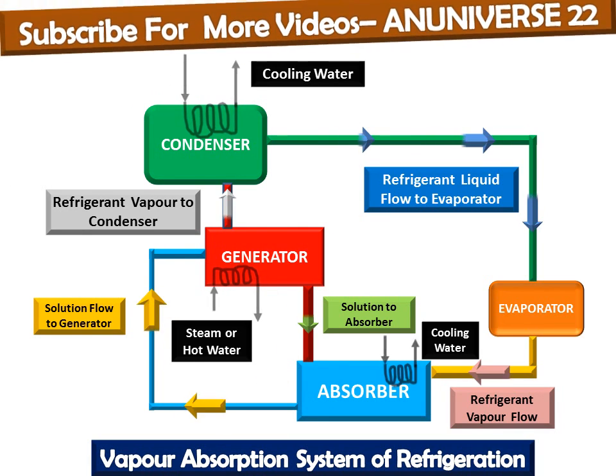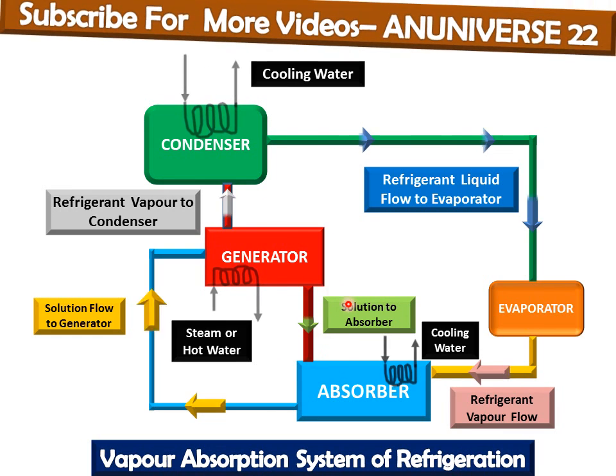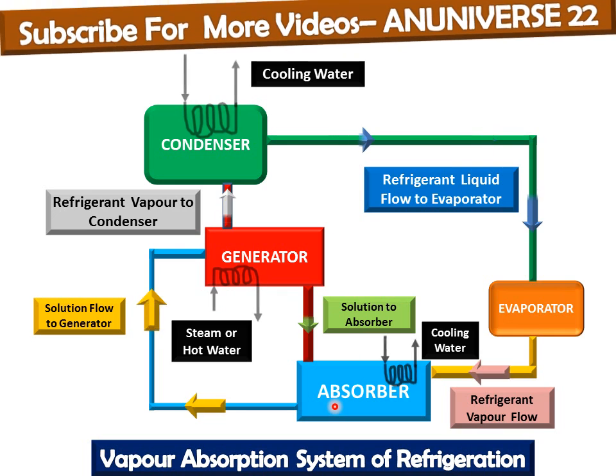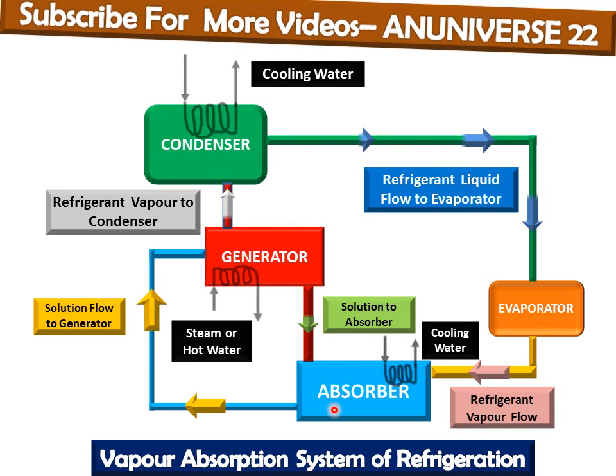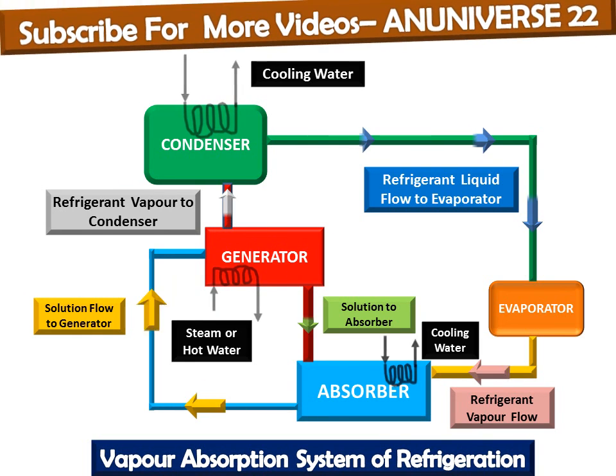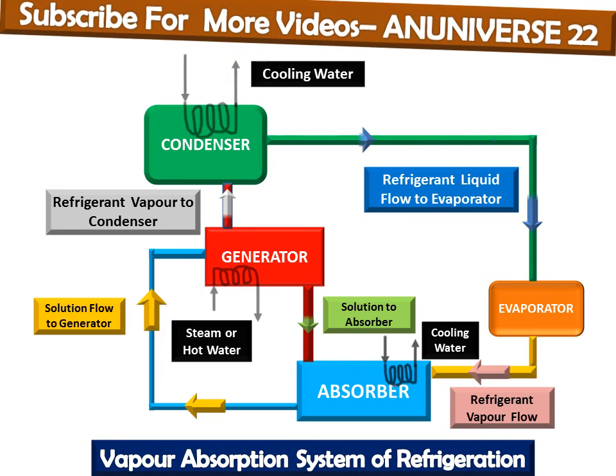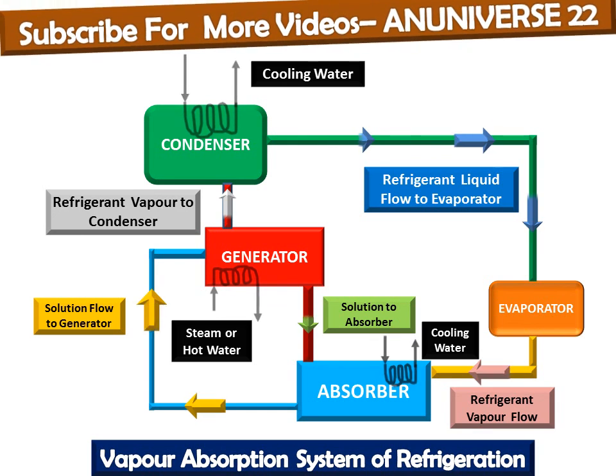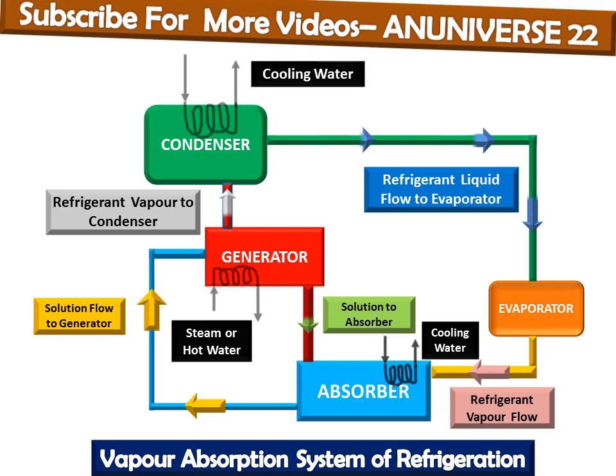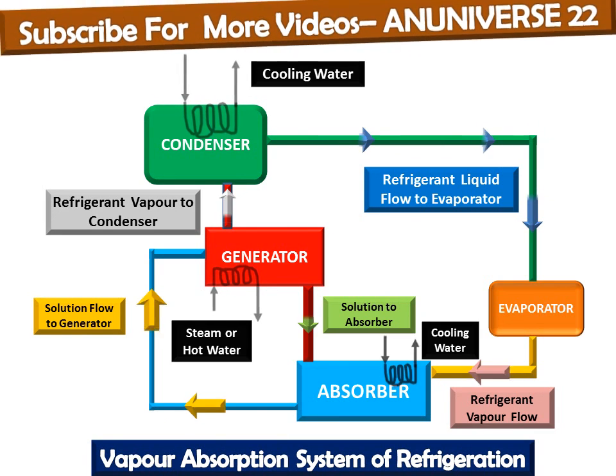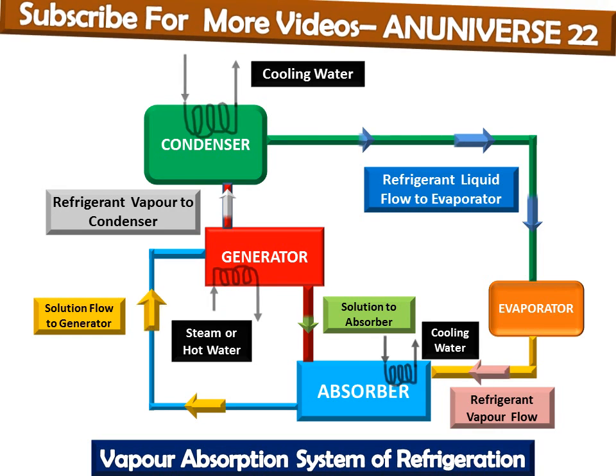An important point: the absorbent solution passing from the generator to the absorber is hot and must be cooled so it can absorb the refrigerant. On the other hand, the absorbent solution sent to the generator is cool and must be heated in the generator for regeneration of the refrigerant. A shell and tube heat exchanger is introduced between the generator and the absorber, though it is not shown in this diagram. Today we have learned about the vapor absorption system of refrigeration, its main parts, how it works, and how it differs from the mechanical vapor compression system.